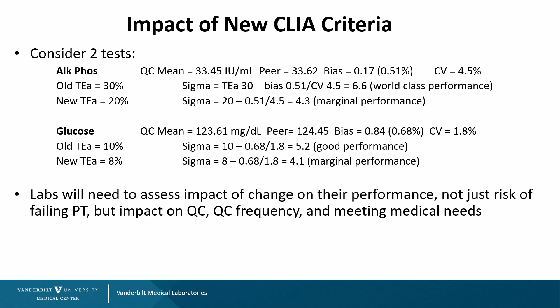Same with glucose. If we have a glucose right at the cutoff for diabetes diagnosis, 123, our peer is reading 124.45, which gives us a bias of about 0.68%. If that imprecision is around 1.8%, and we take an old total allowable error limit of 10%, we're estimating our performance is pretty good. It's 5.2. However, the new total allowable error limit of 8% brings us into marginal performance. So we need to reassess what our risk of failing proficiency testing is based on these new CLIA changes.